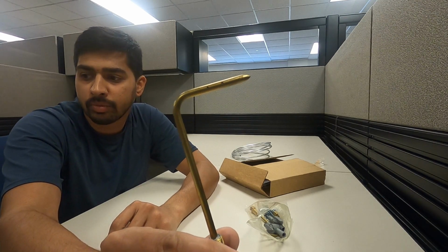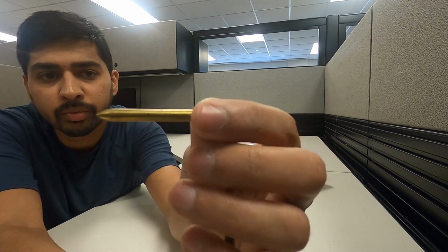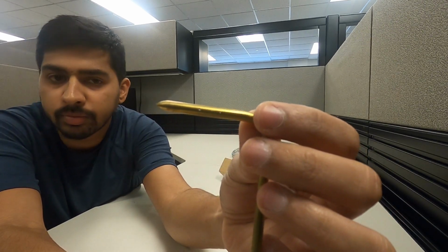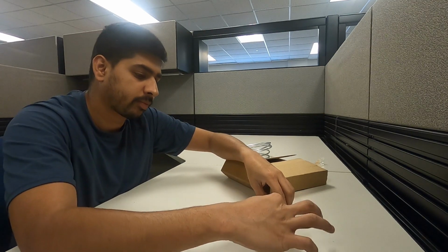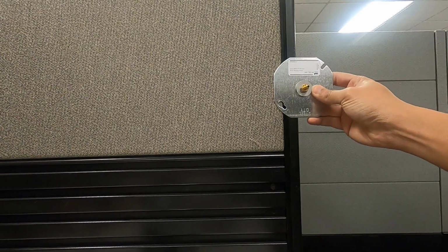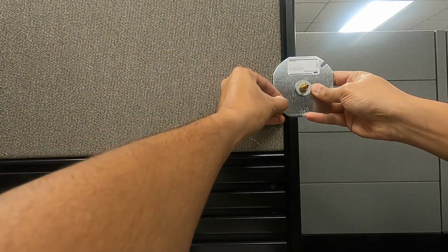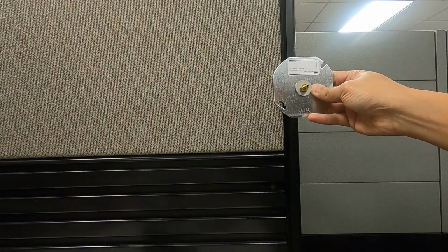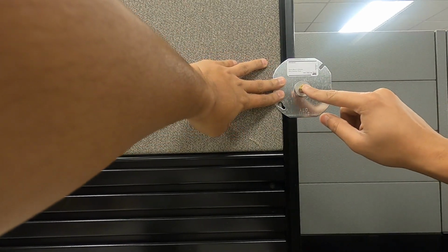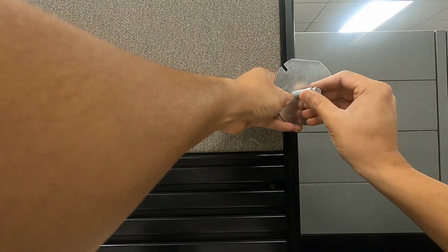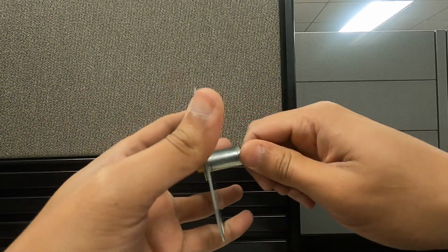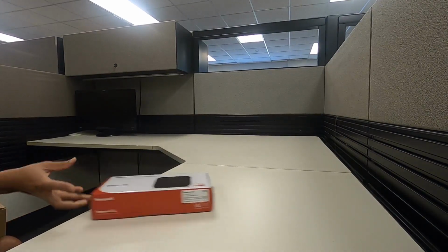So there will be pickup tubes in different accessories. Say it has to go in the duct. You can't just place a straight tube in the duct. You'll have to measure the airflow, the side of the air which is flowing through. So you might have to have a metallic bend, an L bend, where it picks up the airflow coming in. So these are the different types of pressure sensors depending on what applications you're using. You might have to select the accessories required for the respective applications.